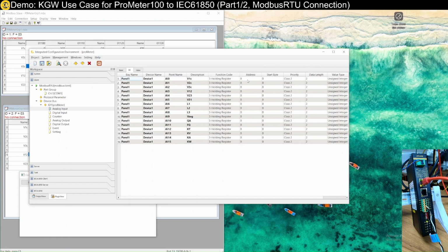The next thing is the address. Right click, and the starting address is 1100. Because it's 2 words, we need to offset by a step of 2. That's why there's always an increment of 2. The data length is in the unit of byte, so now it's 2. The current setting of 2 bytes is equivalent to 1 word, so I need to change this to 4 bytes, which is equivalent to a double word, the 32-bit floating point.